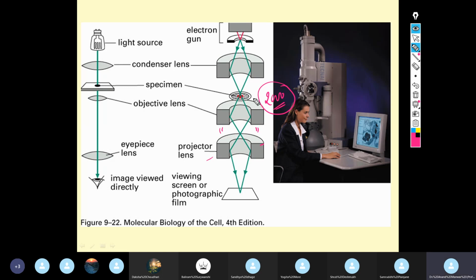Along with that, you will find that within this central column there is a specimen holder. This is the specimen. Just as in a light microscope we place a slide, in a light microscope the glass slide is the specimen holder. Like that, in the case of the electron microscope, you have a specimen holder. Now this electron microscope, as I stated earlier also, uses a thin section which should be electron transparent. So the electron microscope uses a thin specimen, and this thin specimen needs to be handled delicately, and it should be electron transparent. Not only the specimen sample but the holder also. The specimen holder also should be electron transparent.